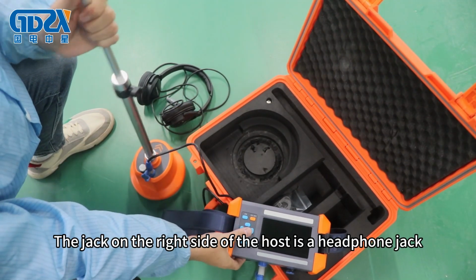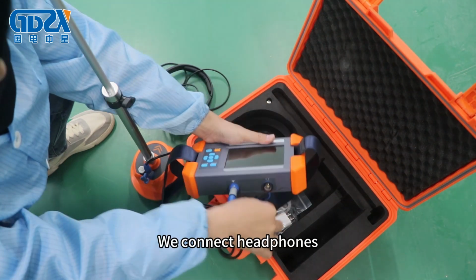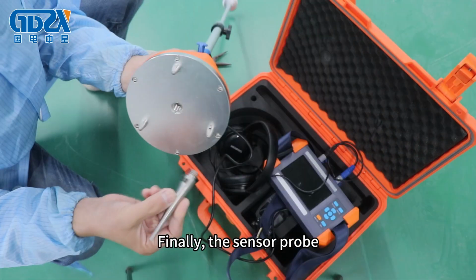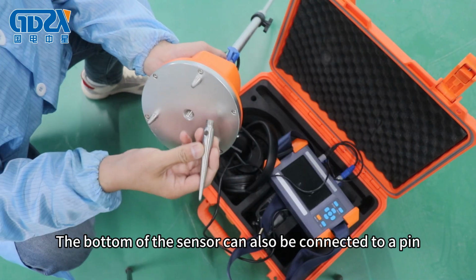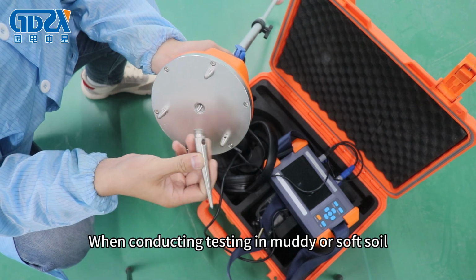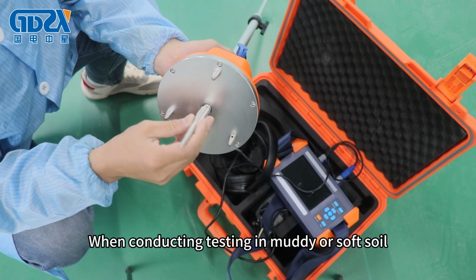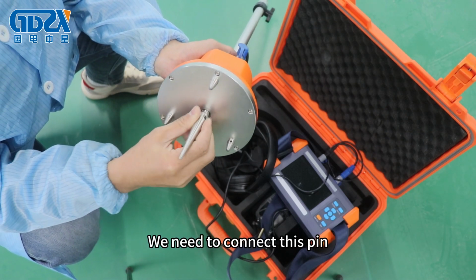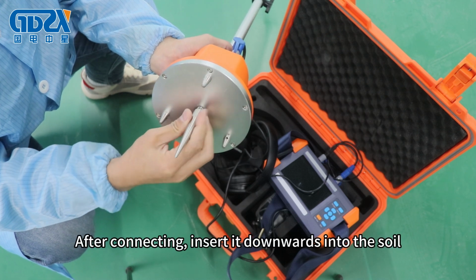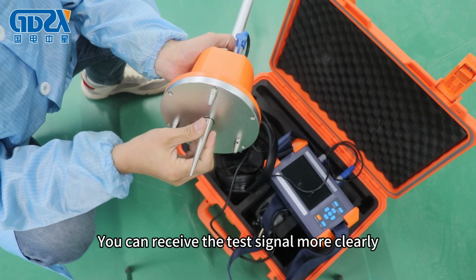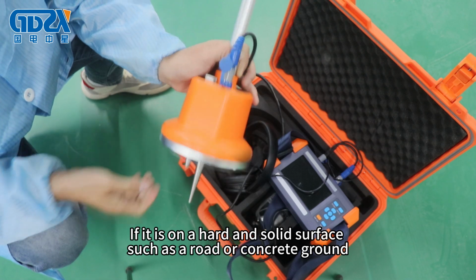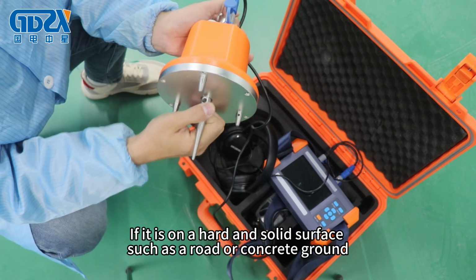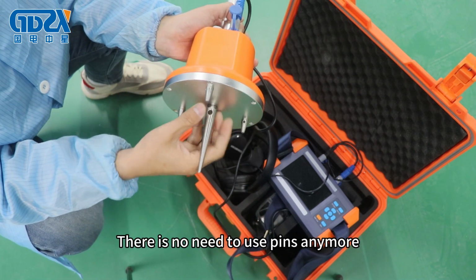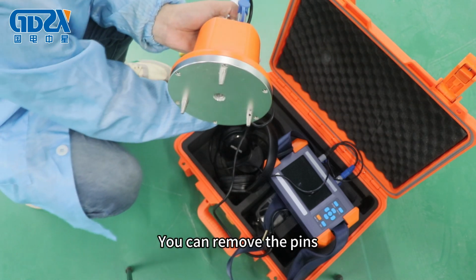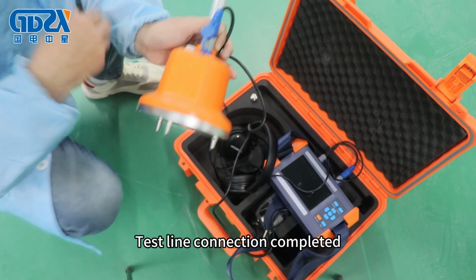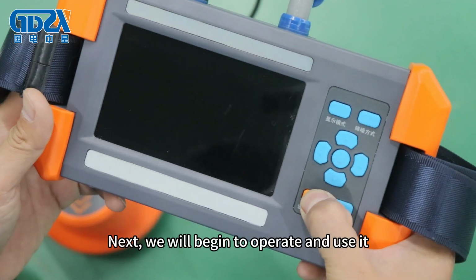The jack on the right side of the host is a headphone jack. We connect headphones. Finally, the sensor probe. The bottom of the sensor can also be connected to a pin. When conducting testing in muddy or soft soil, we need to connect this pin. After connecting, insert it downwards into the soil. You can receive the test signal more clearly. If it is on a hard and solid surface, such as a road or concrete ground, there is no need to use pins anymore. You can remove the pins. Test line connection completed. Next, we will begin to operate and use it.